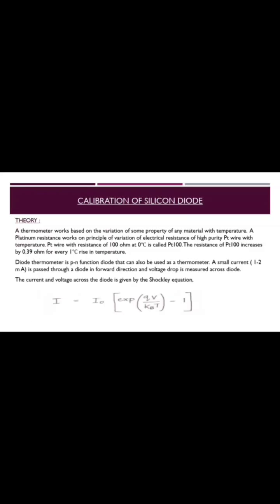a platinum 100 sensor. Coming to the theory of the experiment, a thermometer works based on the variation of some property of any material with temperature. A platinum resistance works on the principle of variation of electrical resistance of high purity platinum wire with temperature. Platinum wire with resistance of 100 ohm at 0 degree Celsius is called PT100. The resistance of PT100 increases by 0.39 ohm for every 1 degree Celsius rise in temperature.